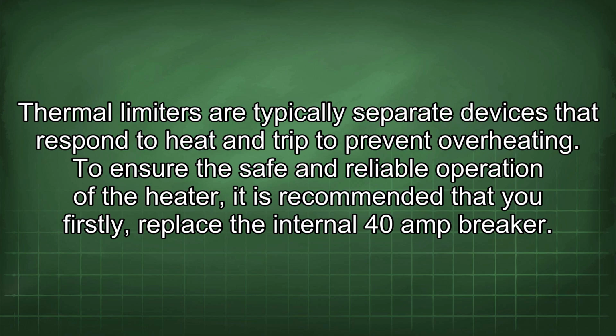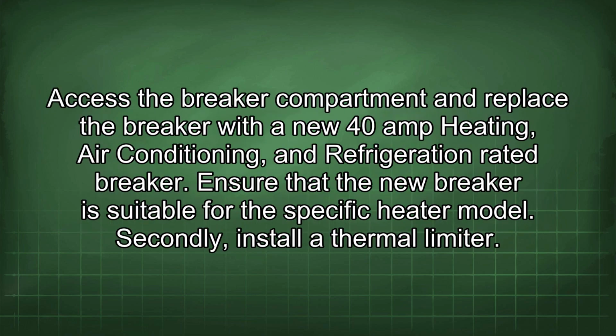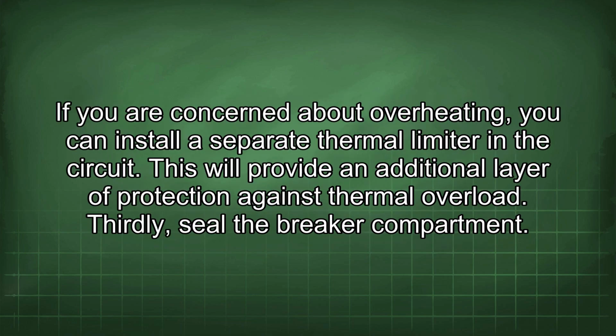To ensure the safe and reliable operation of the heater, it is recommended that you firstly replace the internal 40 amp breaker. Access the breaker compartment and replace the breaker with a new 40 amp heating, air conditioning, and refrigeration rated breaker. Ensure that the new breaker is suitable for the specific heater model. Secondly, install a thermal limiter. If you are concerned about overheating, you can install a separate thermal limiter in the circuit. This will provide an additional layer of protection against thermal overload.